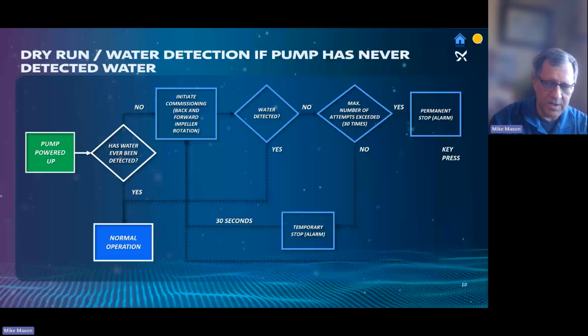If it doesn't, it's going to rotate the impeller back and forth, looking for that feel of water, the wattage that it would expect to see. If it doesn't see it, it'll stop and keep trying, 30 times. Every time it stops, it'll wait 30 seconds, waiting for that water to come in. After 30 attempts, if it still hasn't seen water, it'll go to permanent stop. You have to touch the pump now to re-engage it to try again. Hopefully at that point, somebody realizes that it's dry and will add water to the system.